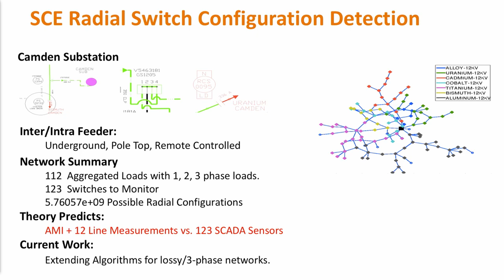We applied that algorithm at this Camden substation at SCE, which has about 112 aggregated loads across different phases and 123 switches to monitor. With our algorithm, we were able to put sensors on only 12 of those switches and still detect the switch configuration of the entire network, even though the switches could change and there are delays in the data. This has been a very promising, computationally expensive, but promising algorithm.